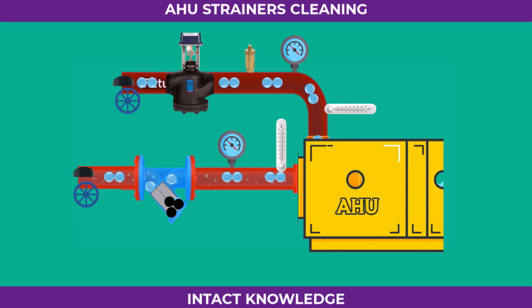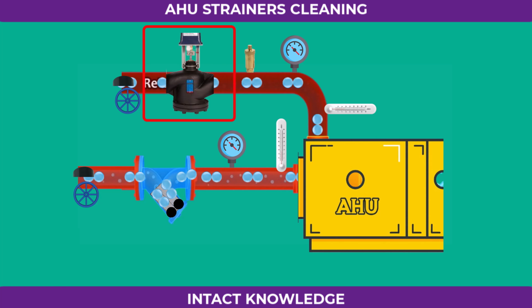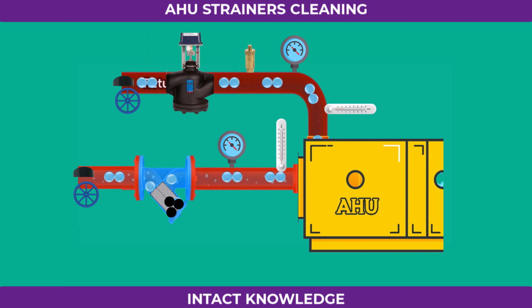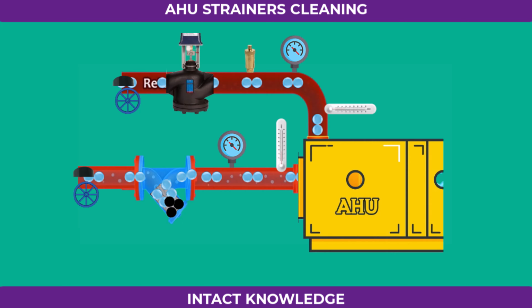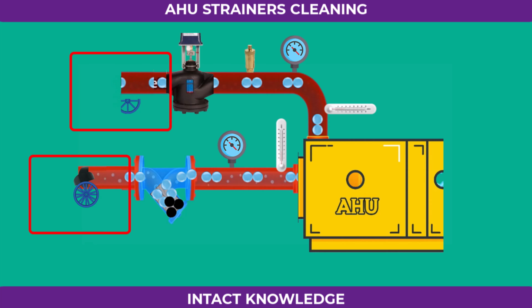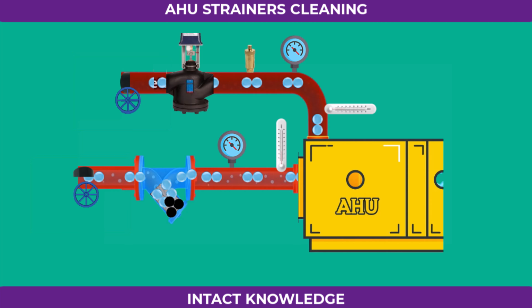To clean the strainer, begin by switching off the AHU. Once the AHU stops, the PICV on the return line will automatically close, cutting off the water flow. Next, close the valve on the return line, followed by the valve on the supply line. After closing both valves, gently open the drain port on the strainer to release any remaining water.